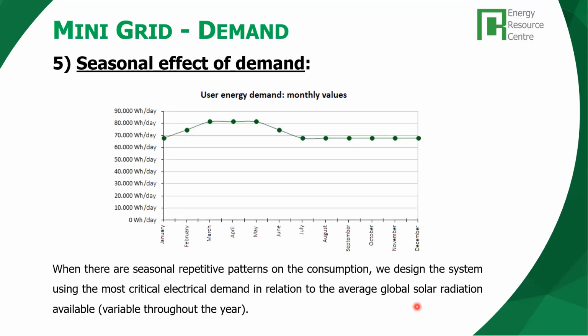Another aspect of the demand and the mini grids is the seasonality. Is the electricity consumption in the village always the same throughout the year, or do we have some patterns? Is there some time of the year where there is a harvest or post-harvest, I don't know, that the electricity demand is higher and then will be lower? This is important for the sizing, because we need to decide which is going to be the demand, the designed demand level that we will use for the sizing of the PV system.